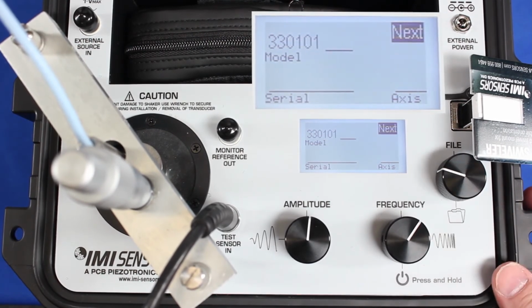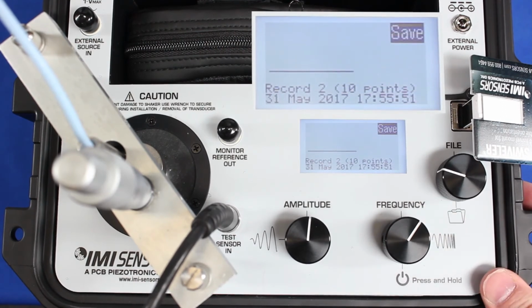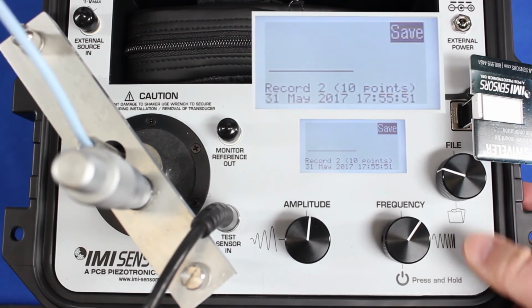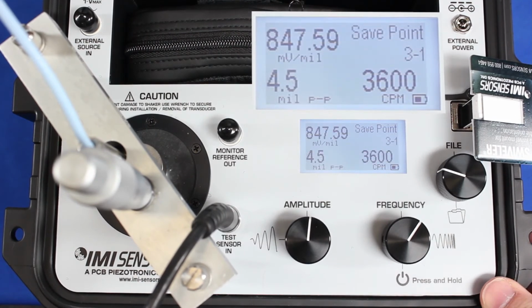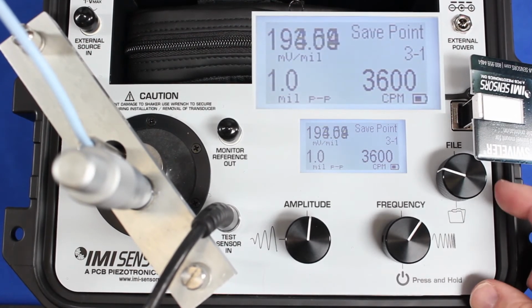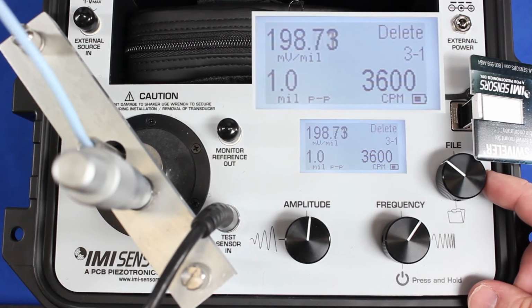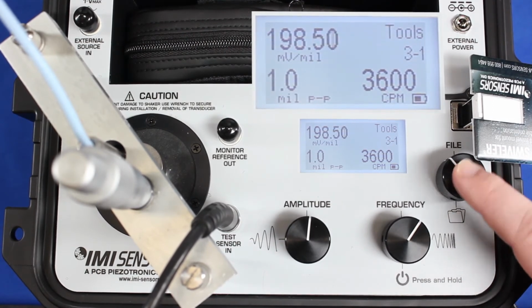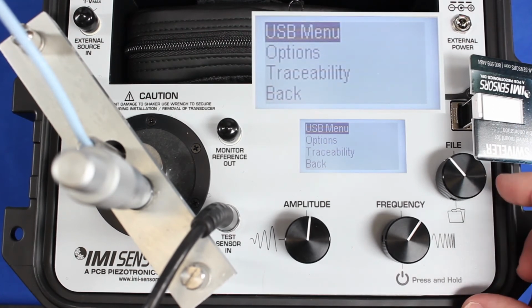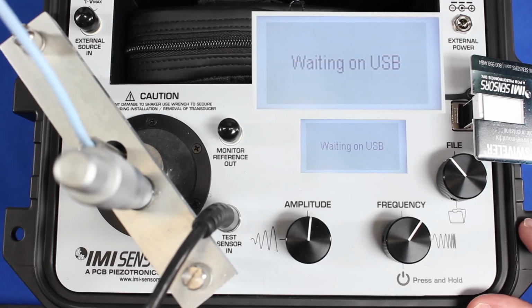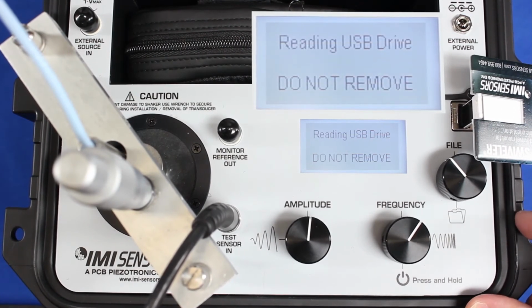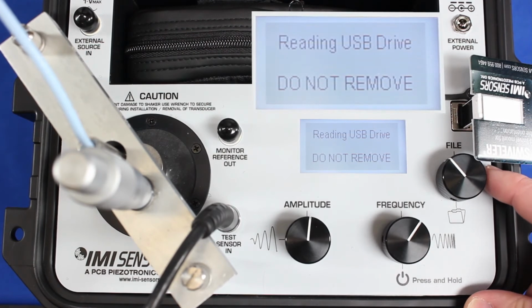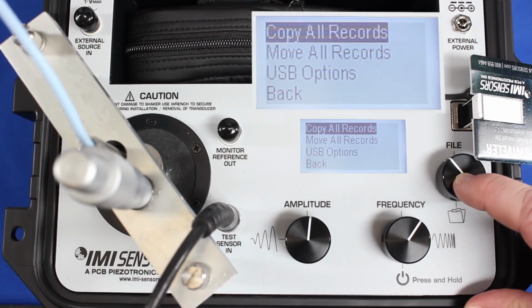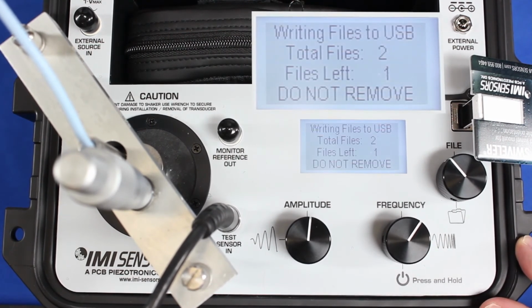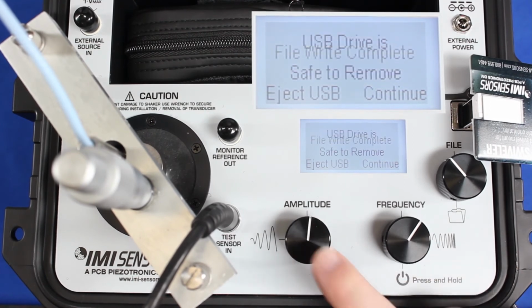On this screen, I can enter my model and serial number if I choose, or I can do so in Microsoft Excel later on, and then I can save the record to the memory of the calibrator by pressing Save. At this point, I can export my saved records to the supplied USB drive by rotating the file button until I see Tools, clicking on the USB menu, and the calibrator will read the USB and give us a copy or move option. I'm going to choose to copy. Copy would copy the records to the USB, and move erases them from the memory of the calibrator and puts them on the USB. I've copied my two records, and I can eject the USB.